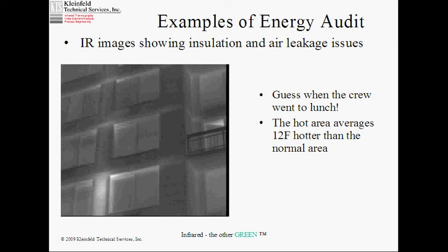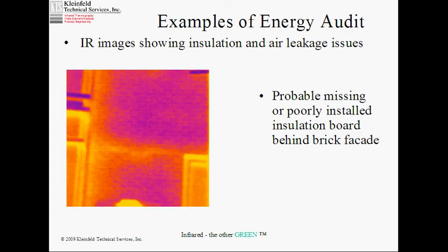Now, I don't know the actual happenstance that led to this, but my supposition is that the crew went to lunch at the bottom of the image and came back 1 floor up and just missed the floor. They did not insulate the outer wall of that pipe chase. It could have been a Monday, Friday thing, too, like, you don't know for sure.